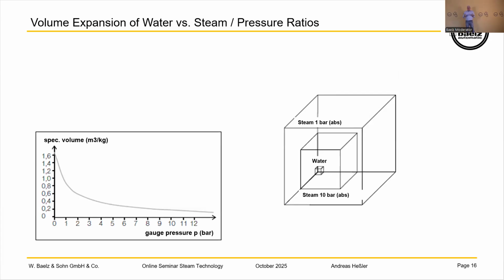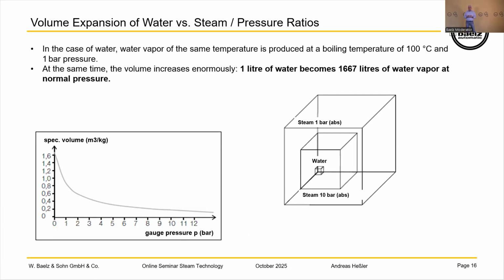Let's have another look. What's very important for me to know is the volume of water and steam. If you have 1 kilogram of water that you heat up, it will have around about 1 liter of volume. If you evaporate this 1 kilogram at 10 bars absolute, you have around about 250 liters. You see the same mass needs much more volume as steam. That's very important for calculating steam pipes, for example.